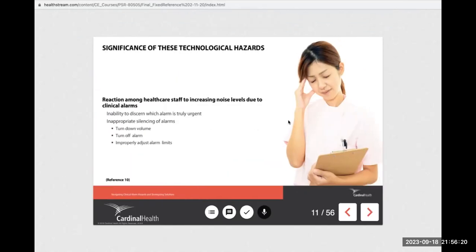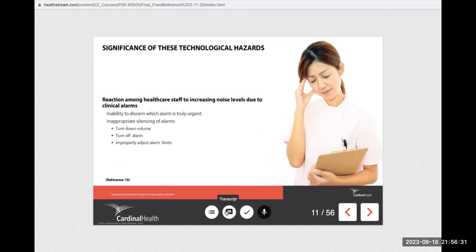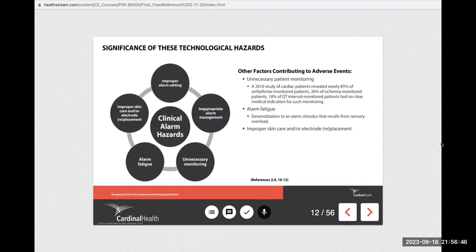The increased noise within clinical units caused by a multitude of alarms has resulted in at least one of two responses. Staff are no longer able to discern which alarm is truly urgent, and/or staff inappropriately silence persistent alarms by turning down the volume, turning them off, or adjusting them outside the appropriate limits. Improper alarm settings and inappropriate alarm management are just two factors that contribute to these adverse events. It should be noted that multiple factors are involved, including unnecessary monitoring of patients, alarm fatigue, and improper skin care and/or electrode placement, replacement.